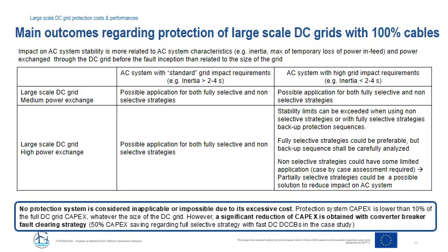Implementing a partially selective strategy by grid splitting could be a possible solution to reduce the impact on the AC system when implementing non-selective protection strategies at quite a low additional cost. Furthermore, it could make it possible to implement different protection strategies in different zones of the grid and therefore facilitate the DC grid protection extensibility. However, it is important to note that such solutions are very case-specific and that the full demonstration of partially selective fault clearing strategies still needs to be completed.